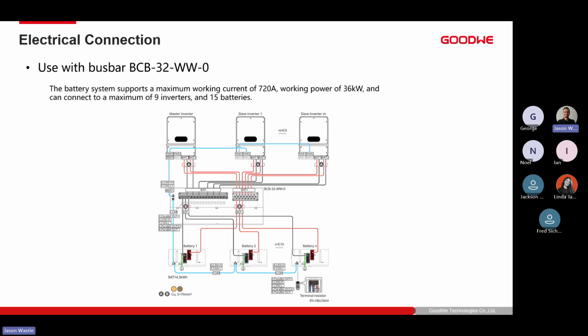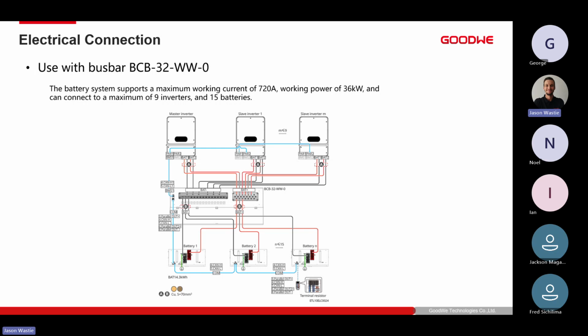If we parallel the system and both battery inputs are being used on one battery stack, we can tell the inverter when commissioning that we are bridging, paralleling the 2 battery inputs, and your BMS cable goes directly into BMS port 1 from the master inverter. The master inverter will then relay all the information and messages onto the slave inverters, and they will be able to see everything and make sure we get the most out of our batteries to keep the system up and running.